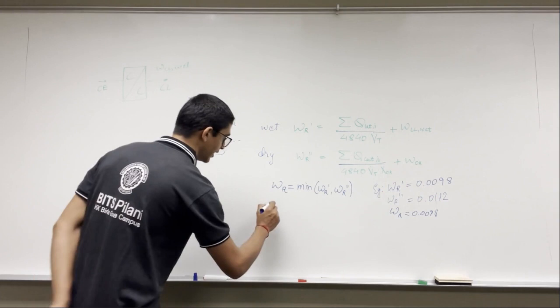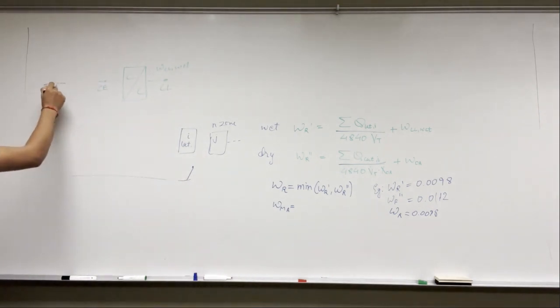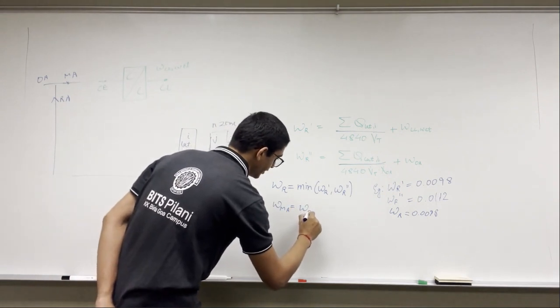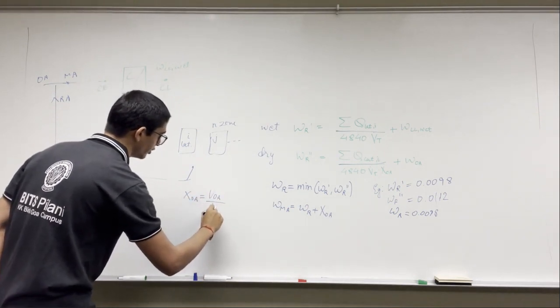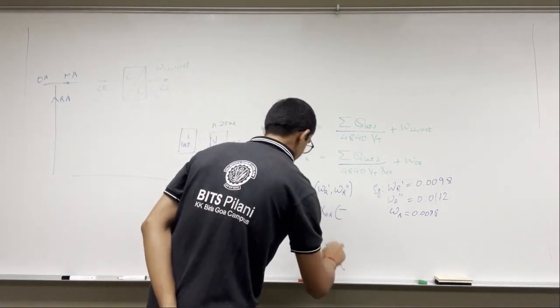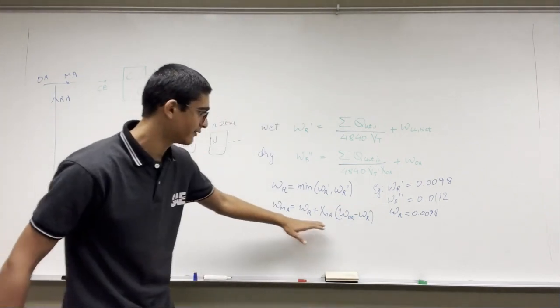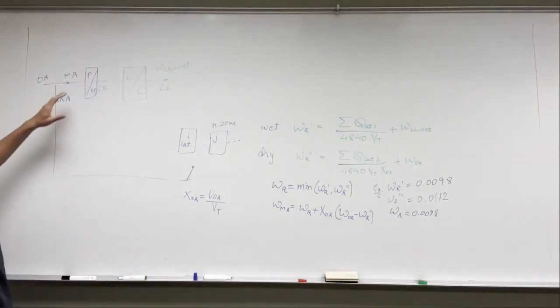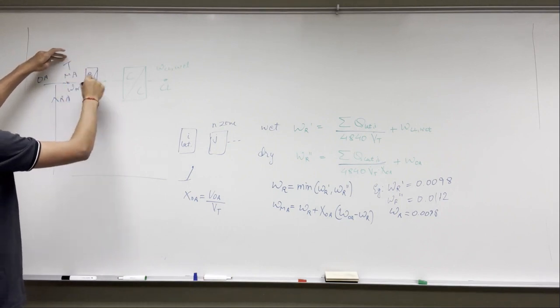Then omega_ma — the mixed air humidity — will be omega of return air plus X_OA times the quantity omega of outside air minus omega of return air. The preheat coil doesn't make any difference because the humidity ratio doesn't change in the preheat coil, so the humidity omega_ma entering the preheat coil is the same as omega_ma leaving it and entering the cooling coil.